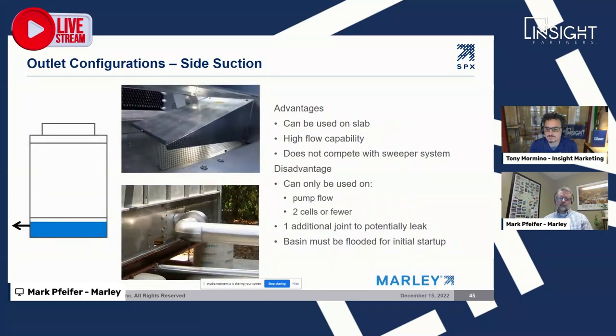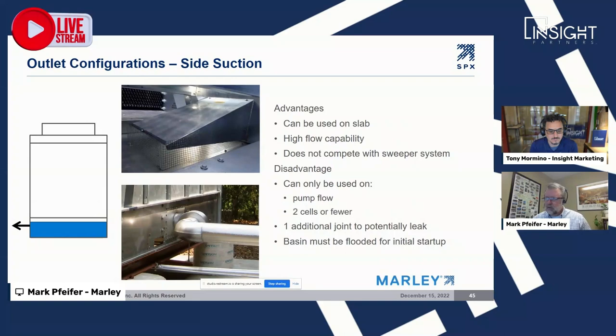The last outlet option is side suction — considered old school and falling out of favor. It was more common when towers were on a slab and it was the only option available. It's not very user-friendly: you have to flood the basin and vent the suction hood during startup. So this option is increasingly losing favor in modern installations.